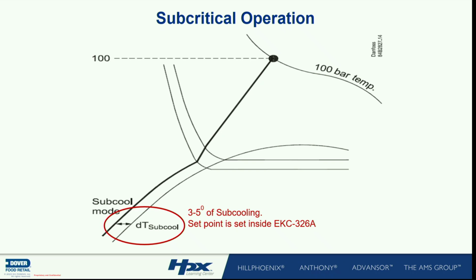So what I'm doing is telling the controller - remember, this line right here, I'll talk about that in a minute, that's my COP line. I'm going to drive this valve based on coefficient of performance, how efficient I can make that system in transcritical. Stop me if I need to clarify. But in mode 1, I'm going to look at it like this.